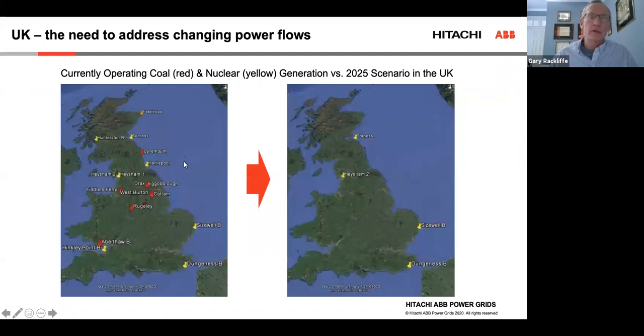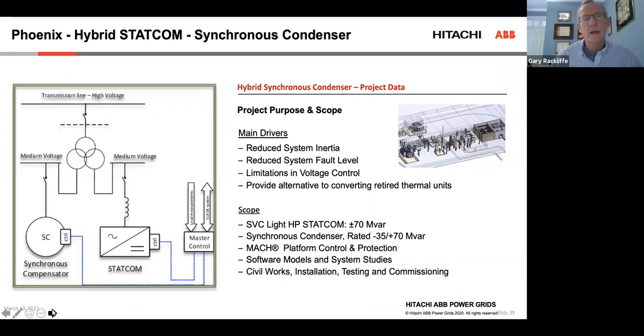And then I just wanted to talk about grid inertia and the changing power flows. This is the UK shown on the left. The yellow is nuclear. The red is coal. This is the current thermal generation in the UK. And you can see by 2025, the coal is gone. So that means we're losing that thermal generation inertia, which is creating concern regarding grid inertia and short circuit capability in the UK. A solution for that is to combine a STATCOM with a synchronous condenser. So you provide the voltage support, but you also provide real power that you can inject into the grid to provide that grid inertia and that short circuit capability. And that's coming from the synchronous condenser. And this is actually a system called Phoenix, which was installed in the UK.